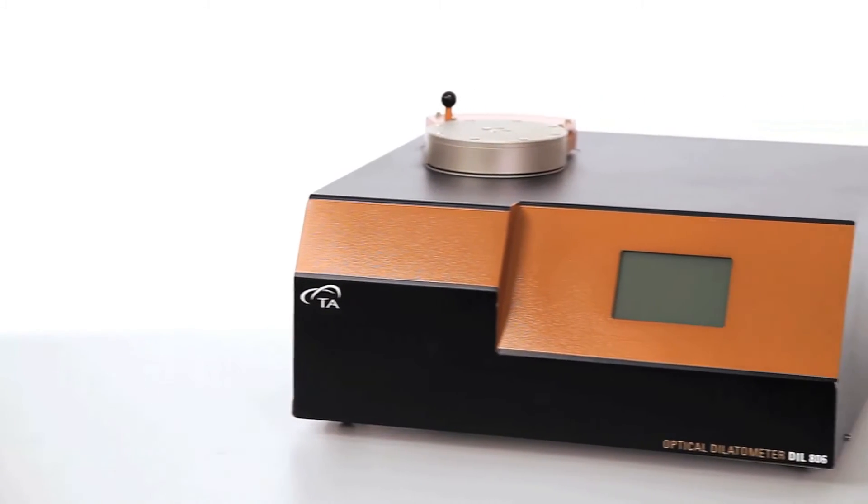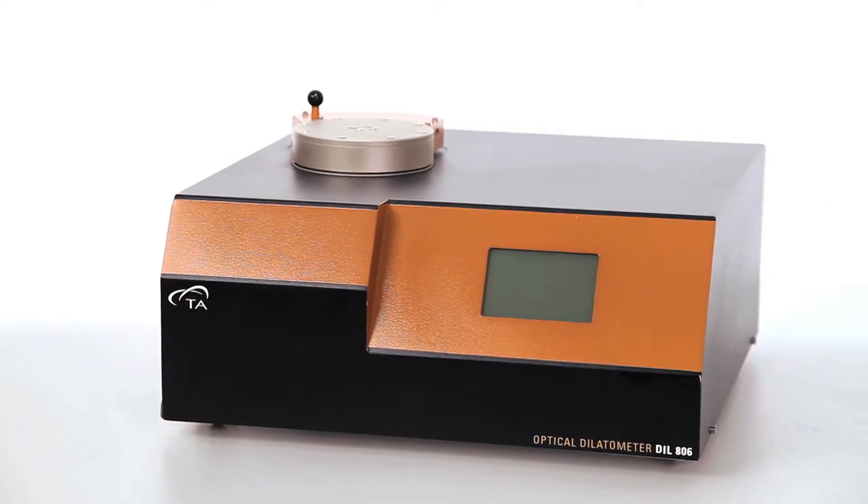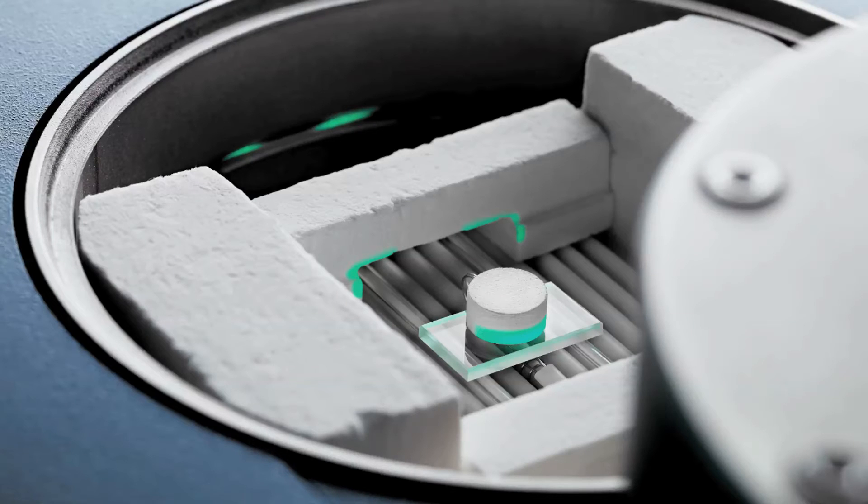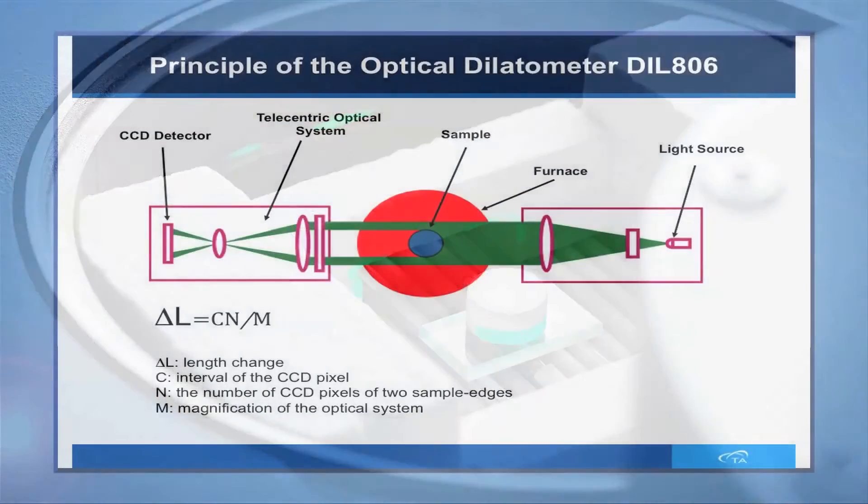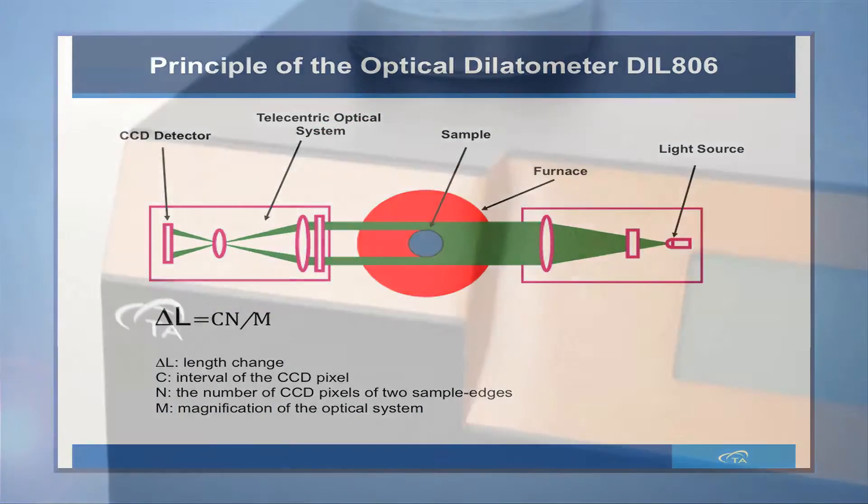The DIL-806 is based upon the shadow meter design. A high-intensity LED light is used on the sample and the thermal displacements are detected through the sample's shadow on the CCD sensor.